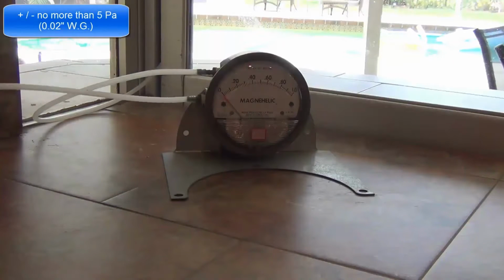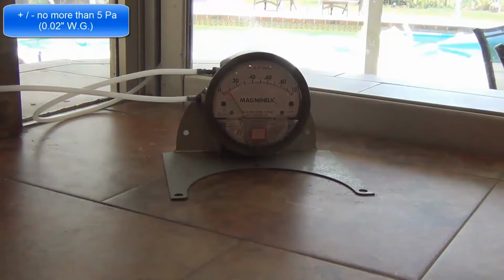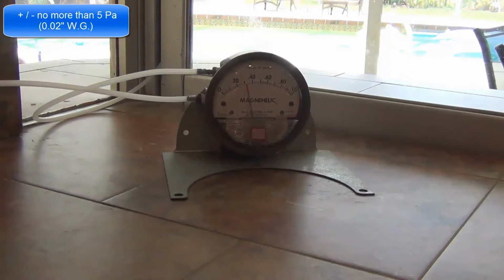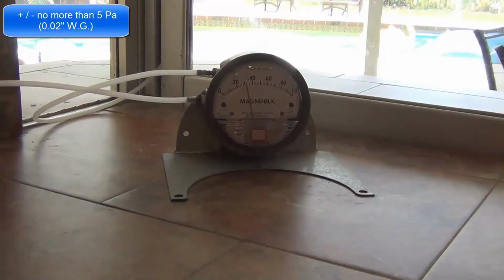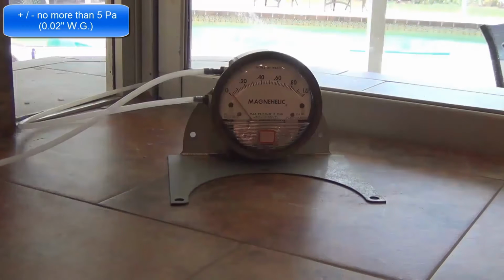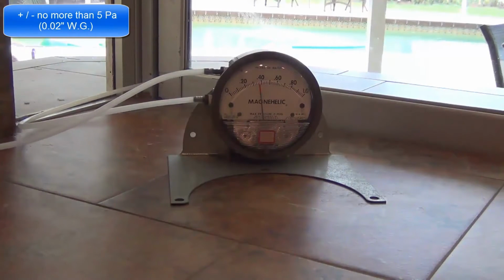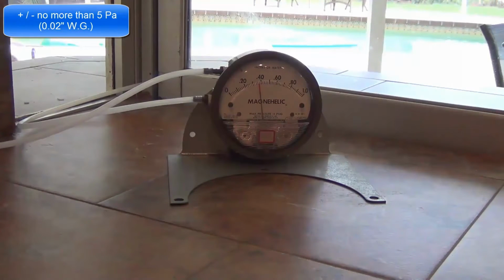Using a pressure differential gauge, measure the house pressure with respect to the outdoors across a door or window. Turn on the exhaust fan and makeup air fan. If the house pressure is positive with respect to the outdoors, slow down the makeup air fan using the high trim pot. If the house is negative with respect to the outdoors, speed up the makeup air fan using the high trim pot. Repeat this procedure for low speed operation. Also repeat this procedure as necessary until the system automatically operates as required at high, low and all intermediate speeds.